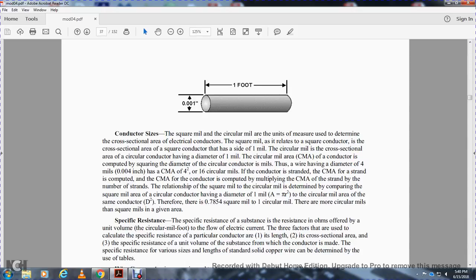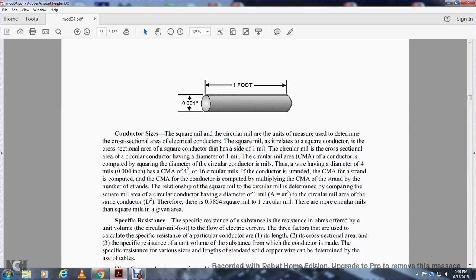Circular mil area, or CMA, of a conductor is determined by squaring the diameter of a circular conductor in mils. For example, a wire having a diameter of 4 mils has a CMA, or circular mil area, of 4 squared, which equals 16 circular mils.